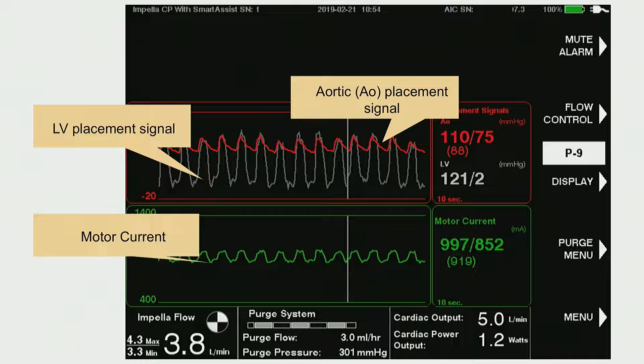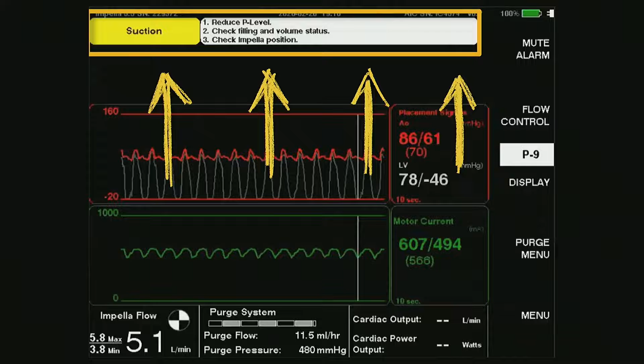Because alarms are going to be inevitable. You're going to start having alarming and people are going to panic, but there's no reason to panic because the machine will help you out. What I mean by that is a type of alarm is a suction alarm. But the good thing is that when you do have these types of alarms, the device will actually tell you what to do. So reduce the P level, check the filling, check the placement, things like that. The machine will tell you what the issue is.